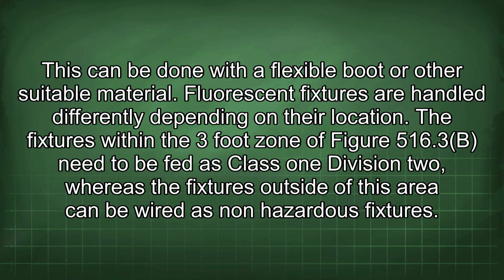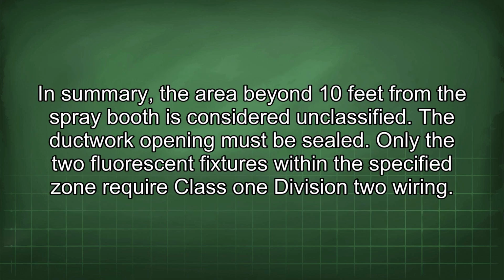Fluorescent fixtures are handled differently depending on their location. The fixtures within the 3-foot zone of Figure 516.3(b) need to be fed as Class 1 Division 2, whereas the fixtures outside of this area can be wired as non-hazardous fixtures. In summary, the area beyond 10 feet from the spray booth is considered unclassified. The ductwork opening must be sealed. Only the two fluorescent fixtures within the specified zone require Class 1 Division 2 wiring.